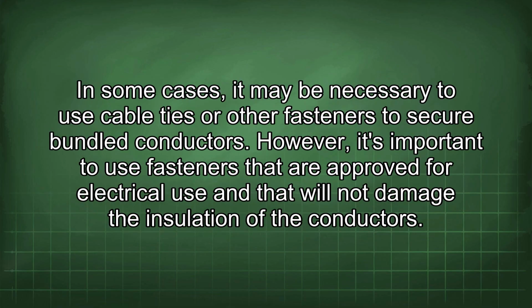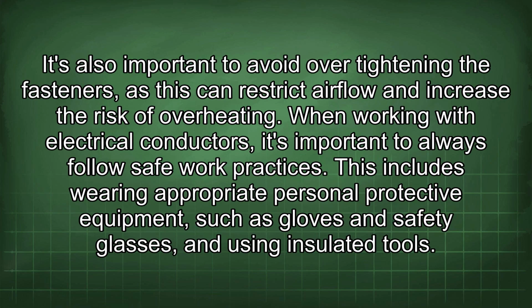In some cases, it may be necessary to use cable ties or other fasteners to secure bundled conductors. However, it's important to use fasteners that are approved for electrical use and that will not damage the insulation of the conductors. It's also important to avoid over-tightening the fasteners, as this can restrict airflow and increase the risk of overheating. When working with electrical conductors, it's important to always follow safe work practices.